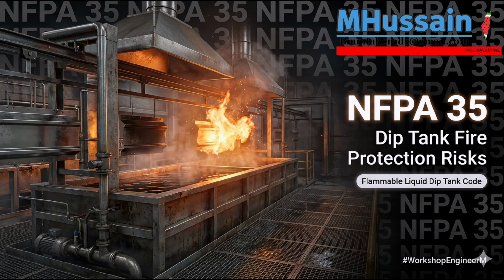Exactly. The investigation must ask the hard questions. Why was there a concentrated flammable vapor cloud lingering on the floor in the first place? Did the mechanical floor sweeping ventilation system fail? Why was the solvent spilled and why wasn't it cleaned up? And why a steel wrench? Right. Why was a spark-producing steel wrench being used in a Division I area instead of a non-sparking brass tool?